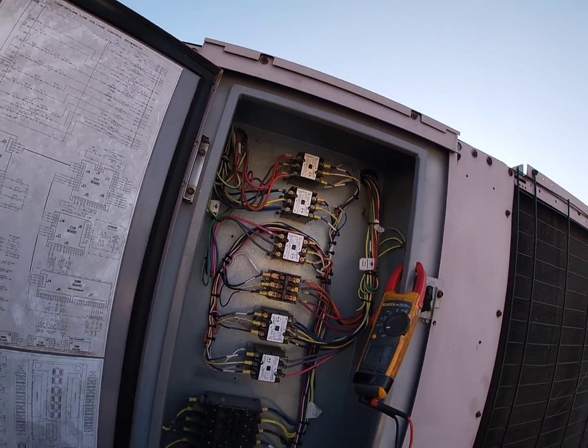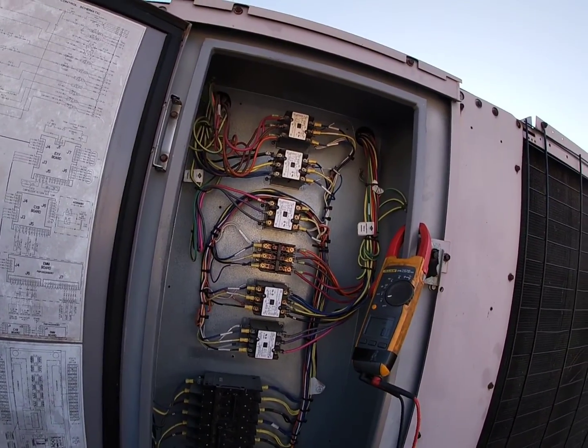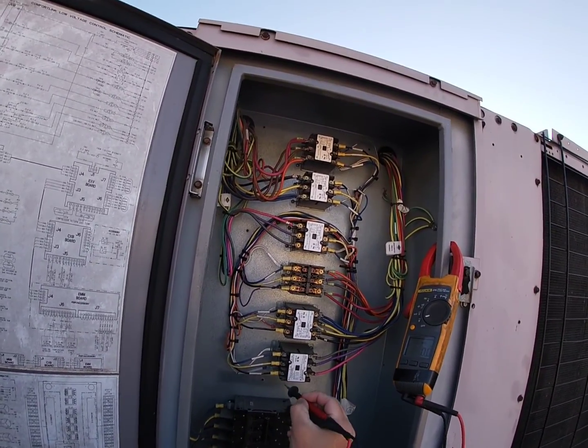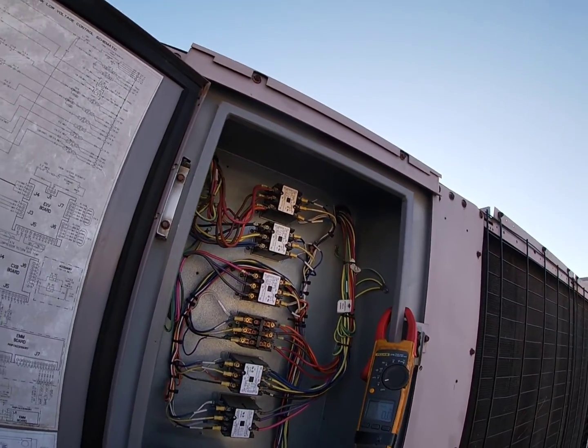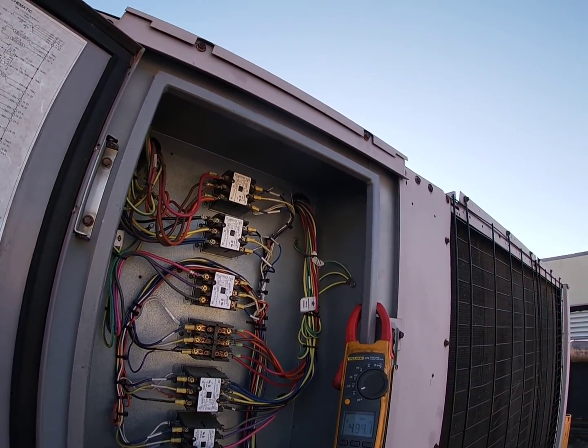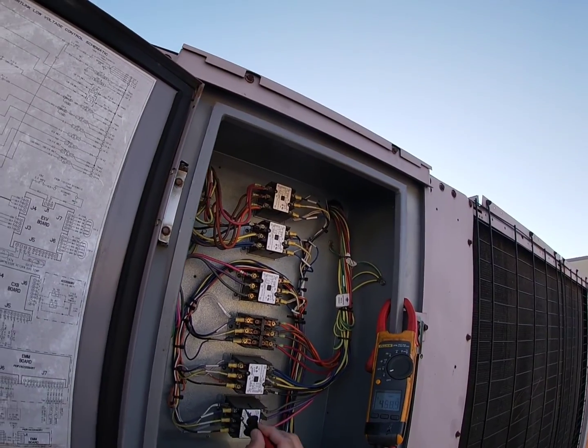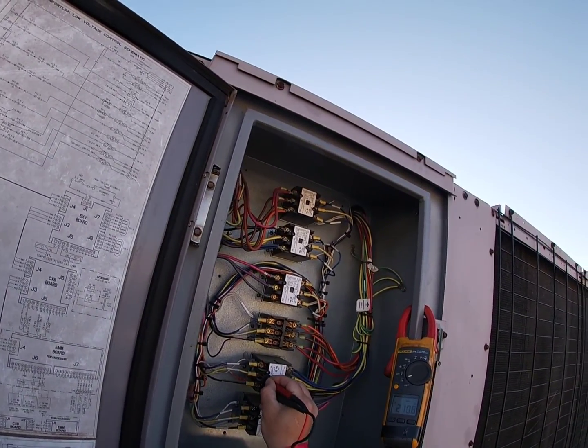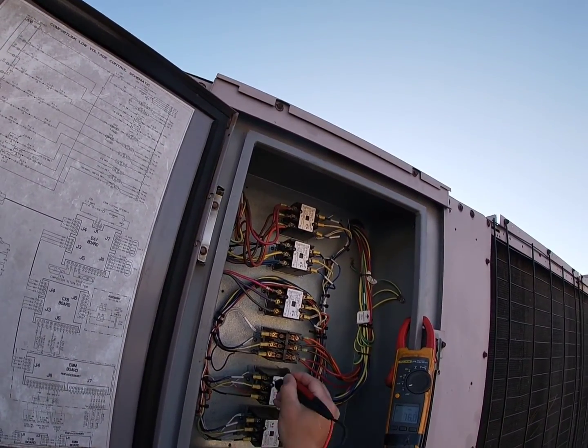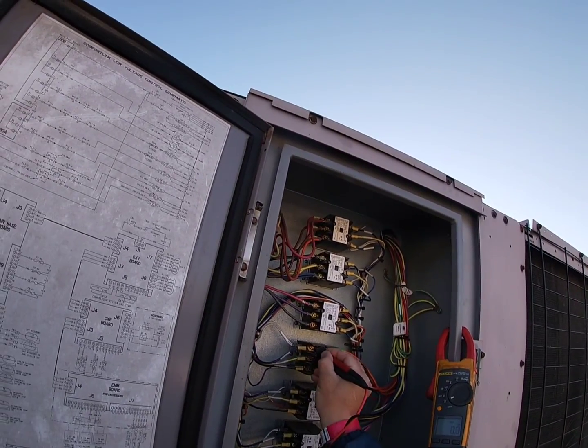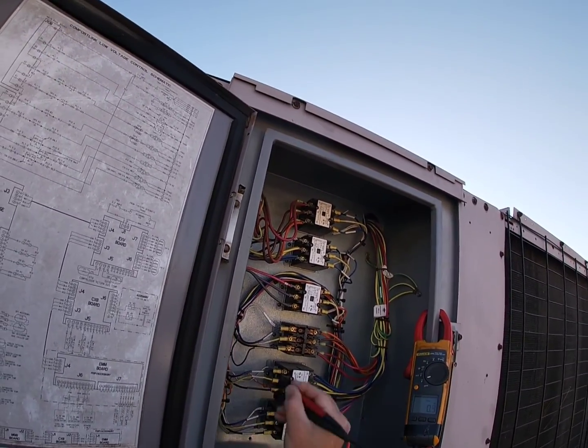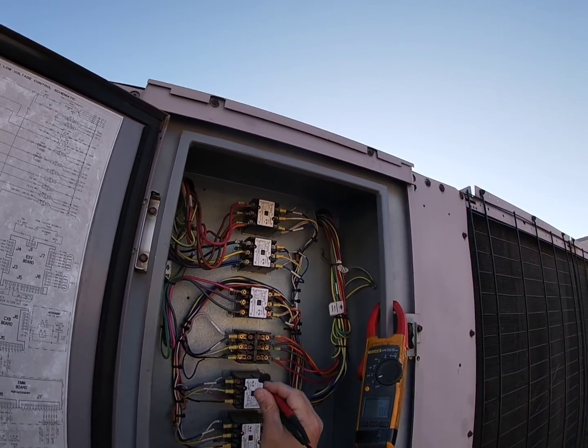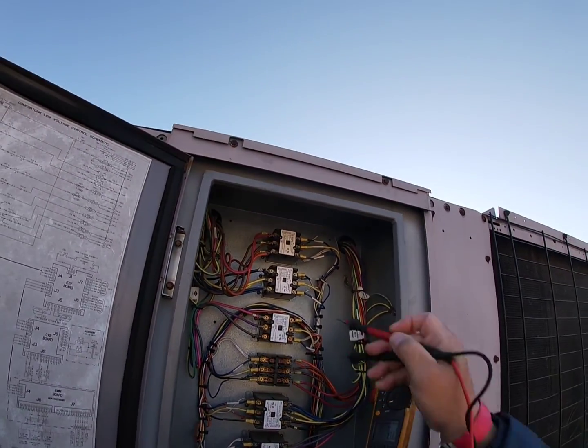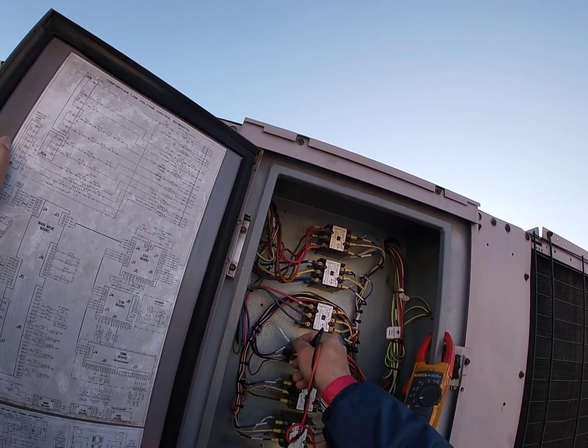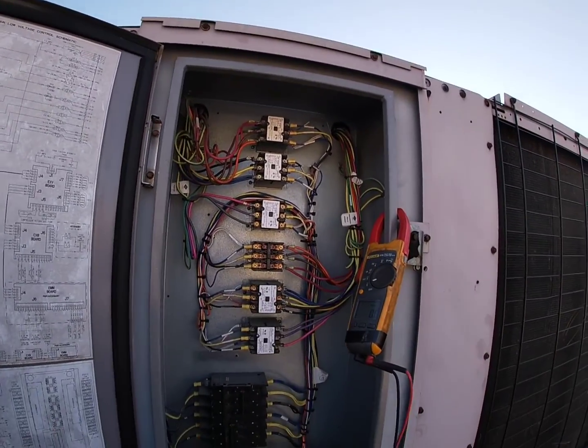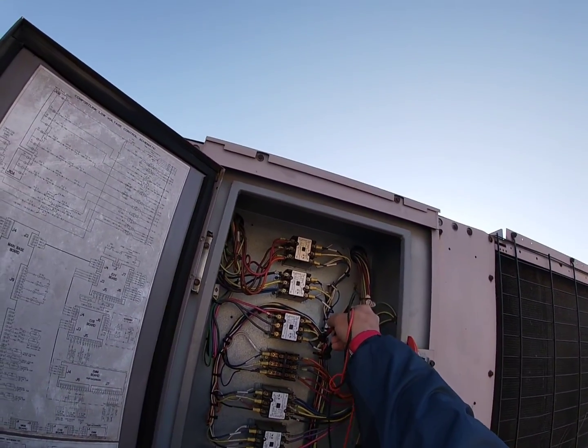So we're gonna see which of these breakers feed what contactor here. So obviously we're not gonna have power on the line side, so I have it on voltage there. Okay, I got power here, so this is for this breaker. I got power here, that's for that breaker. I got power here, so that's for that breaker. So on this side it could get a little confusing. You guys want to double check this, but we're obviously following blue, yellow, and black just like it is over here. So it's going to be on this side here.